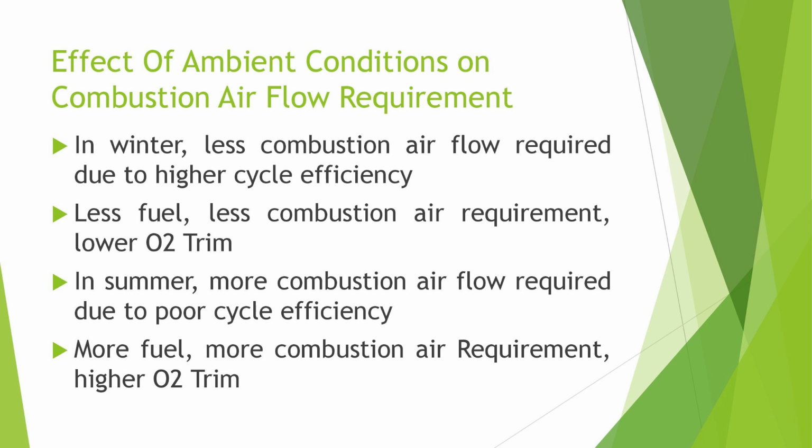Effect of ambient conditions on combustion air flow requirement. In winter, less combustion air flow is required due to higher cycle efficiency. Less fuel, less combustion air requirement, lower O2 trim. In summer, more combustion air flow is required due to poor cycle efficiency. More fuel, more combustion air requirement, higher O2 trim.